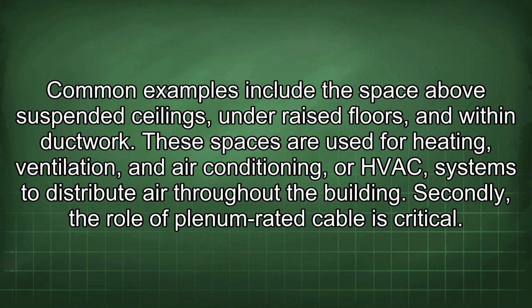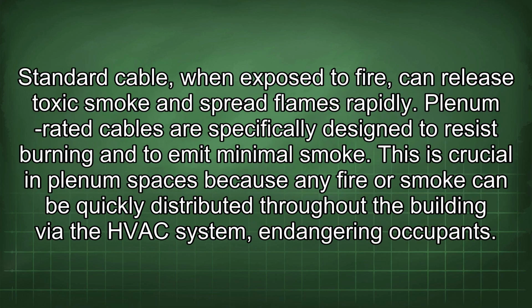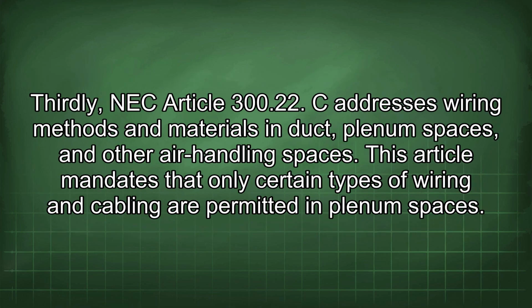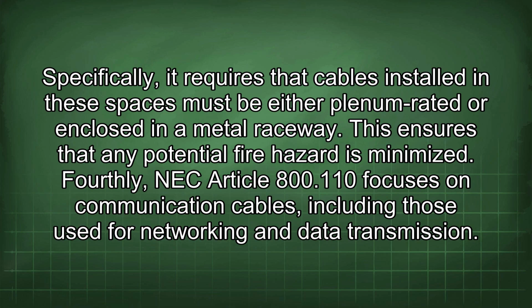Secondly, the role of plenum-rated cable is critical. Standard cable, when exposed to fire, can release toxic smoke and spread flames rapidly. Plenum-rated cables are specifically designed to resist burning and to emit minimal smoke. This is crucial in plenum spaces because any fire or smoke can be quickly distributed throughout the building via the HVAC system, endangering occupants. Thirdly, NEC Article 300.22 C addresses wiring methods and materials in duct plenum spaces and other air handling spaces. This article mandates that only certain types of wiring and cabling are permitted in plenum spaces. Specifically, it requires that cables installed in these spaces must be either plenum-rated or enclosed in a metal raceway. This ensures that any potential fire hazard is minimized.